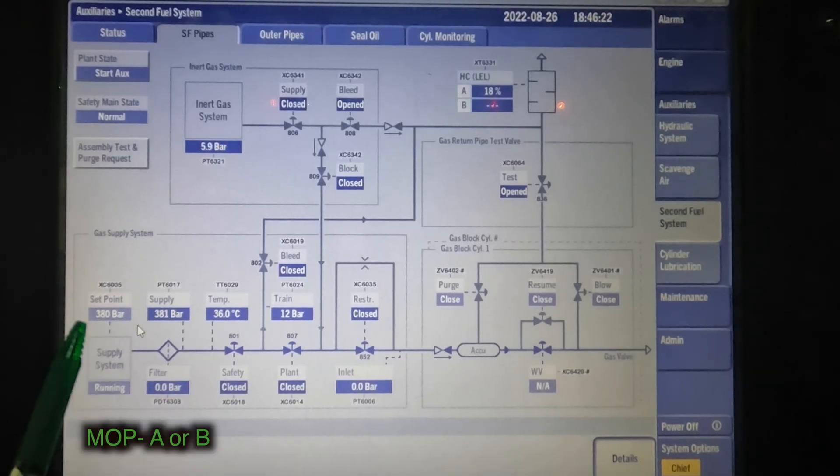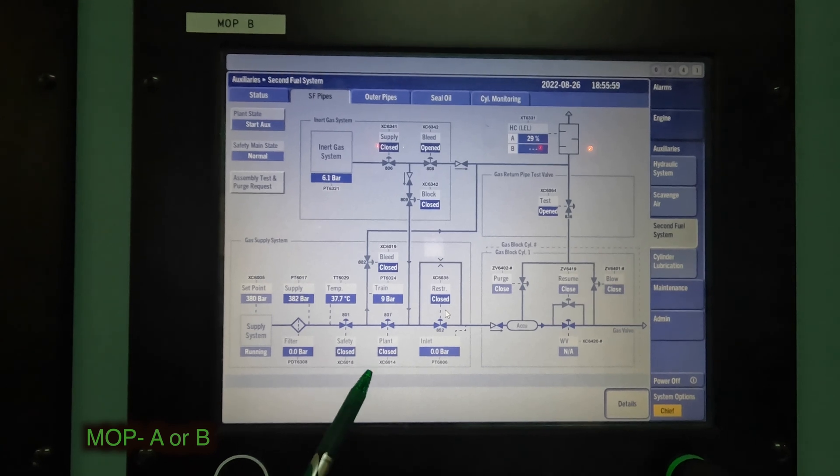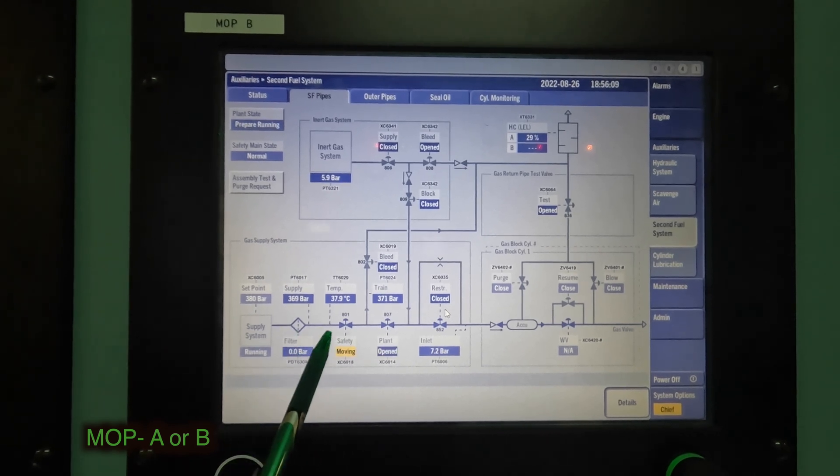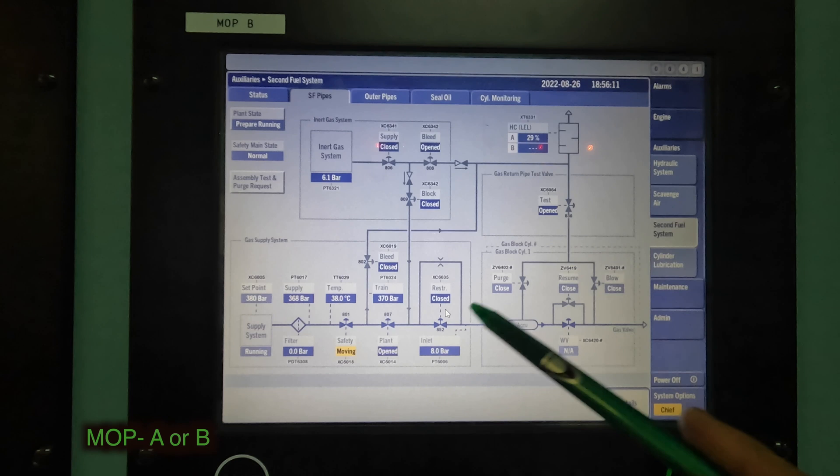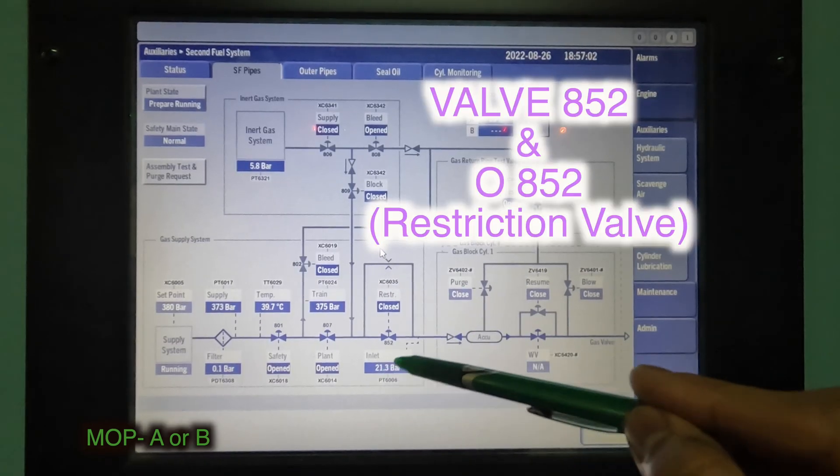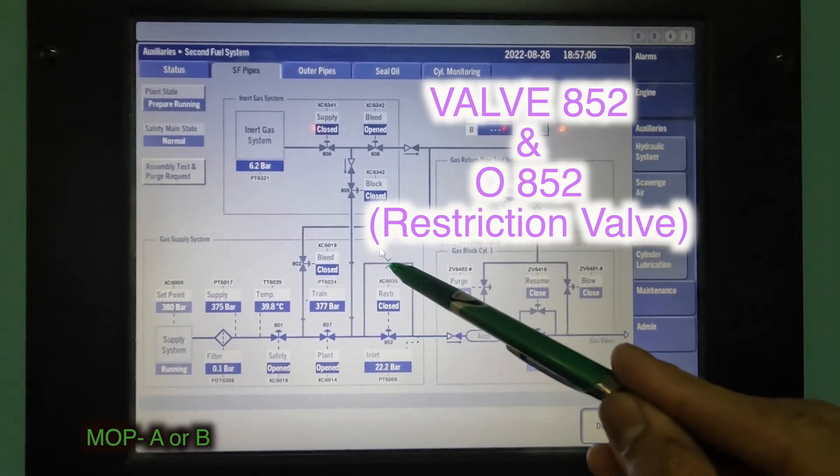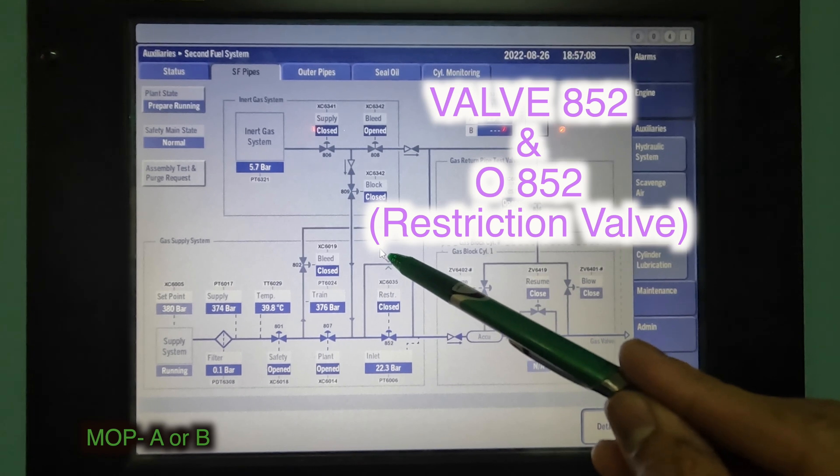Once the pressure reaches 385 bar, now we should get the signal to these valves to open. So the gas will start moving here across the orifice in the restriction valve. So this whole thing together, it is called as 852. 852 the main valve, and here we have 0852 which is the orifice or restriction 852.